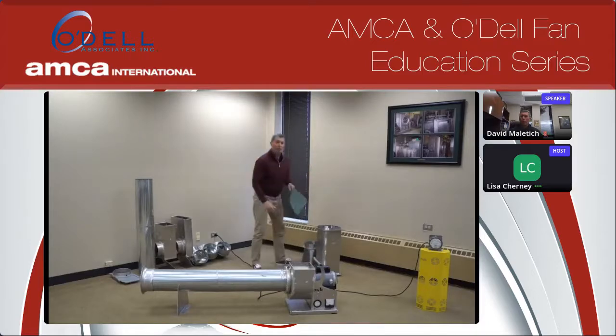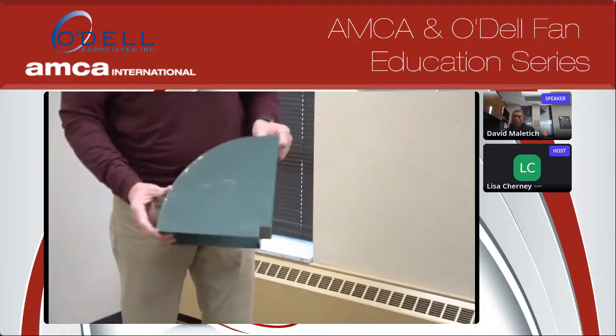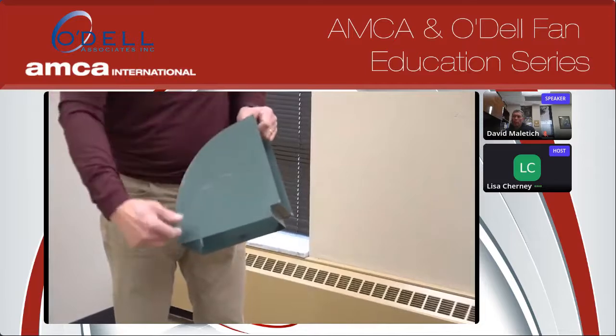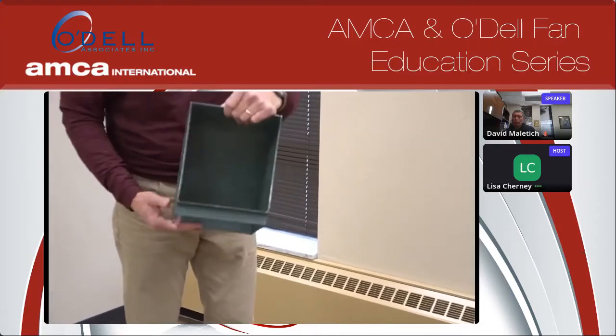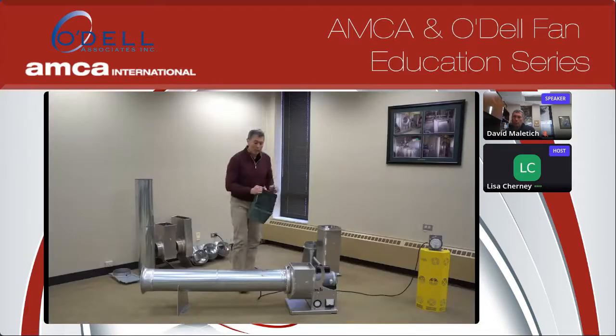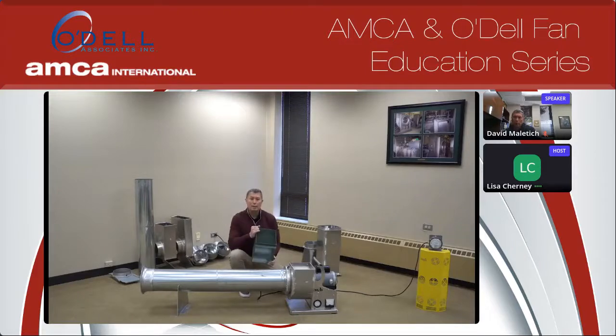At the discharge of the fan, if you have an elbow, like this 90 degree, there's a proper way to have the elbow orientated and there's an improper way. The improper way is to put it where it breaks the back of the air. The fan has a volute shape. Most of the air discharges on this side of the housing, or the outside of the volute shape. And if we put an elbow that breaks the volute shape or goes against it, air pressurizes here, gets deadheaded, and has to get reaccelerated back out.